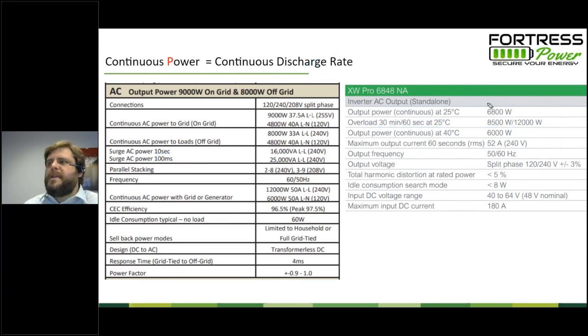What that means is, if you subject this 6.8 kilowatt inverter to an 8 kilowatt load, it'll actually run for 30 minutes before turning off. This other inverter may not be able to run above the 9 kilowatt grid tied or 8 kilowatt off grid rating. Anything harder than that, it will turn off. So actually these two inverters are a little bit closer in terms of real performance than might meet the eye, given that this one can surge to 8 kilowatts for a short duration.